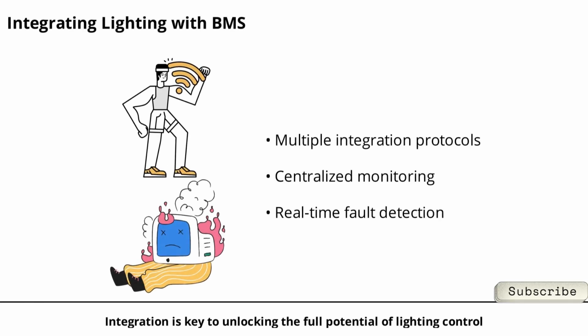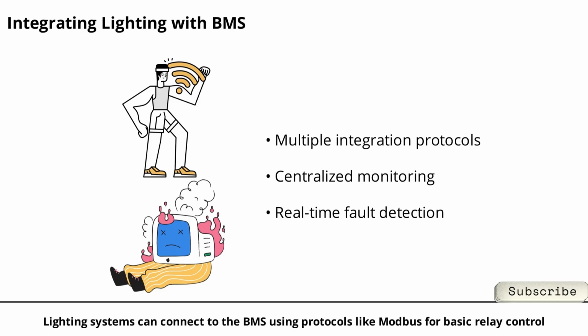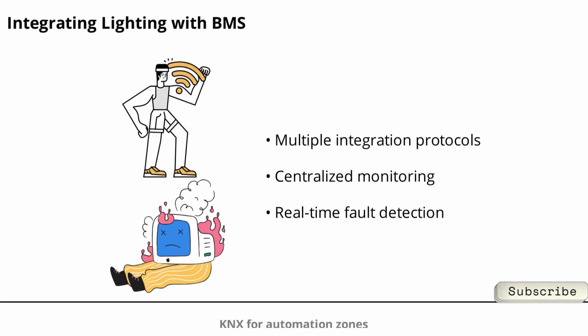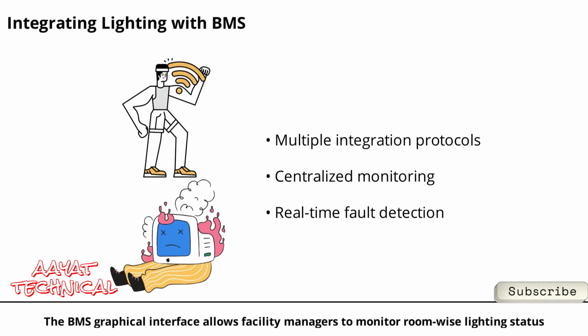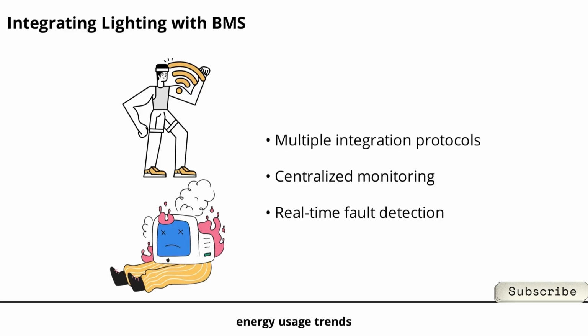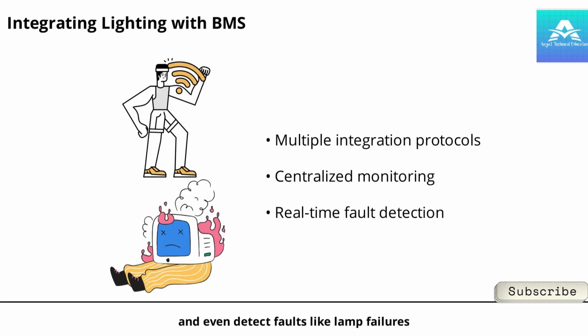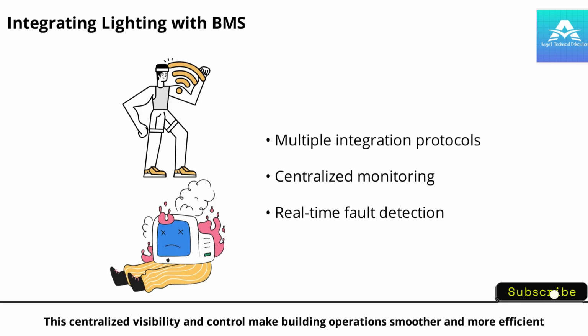Integration is key to unlocking the full potential of lighting control. Lighting systems can connect to the BMS using protocols like Modbus for basic relay control, BACnet/IP for smart controllers, KNX for automation zones, and DALI for individual lamp addressing. The BMS graphical interface allows facility managers to monitor room-wise lighting status, real-time occupancy, energy usage trends, and even detect faults like lamp failures. This centralized visibility and control make building operations smoother and more efficient.